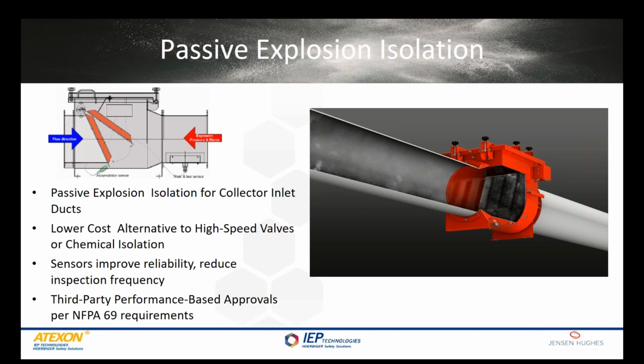Now, there are some NFPA 69 minimum prescriptive requirements for the design and implementation of these styles of valves. The first and maybe most important one is they do have to be third-party performance-based tested and approved for the intended use as an explosion isolation device. So they have to be tested and approved for use in explosive conditions to make sure that they are going to stop that flame. Make sure that they're strong enough to hold up to that pressure that's going to come back through the duct. These valves have become much more popular in recent years.